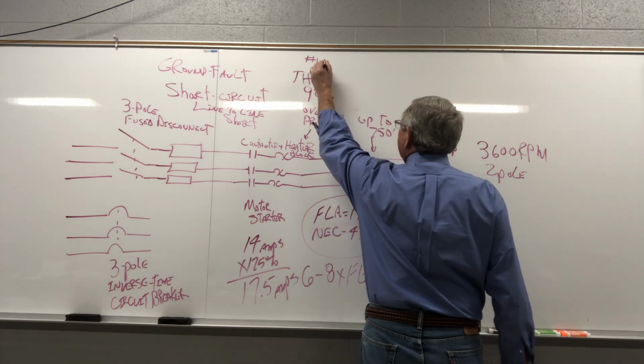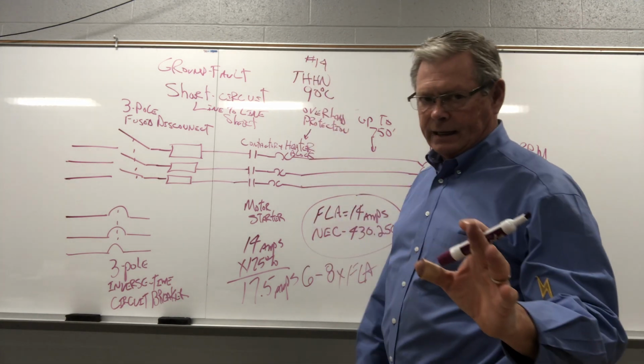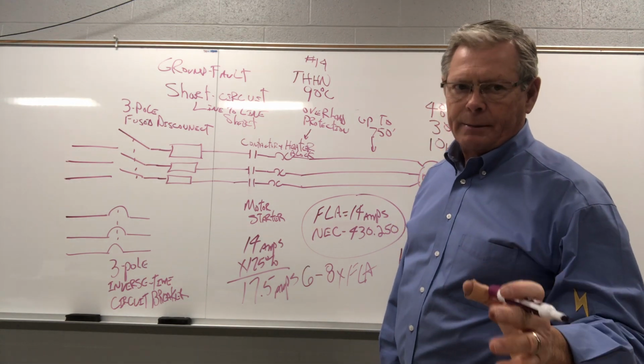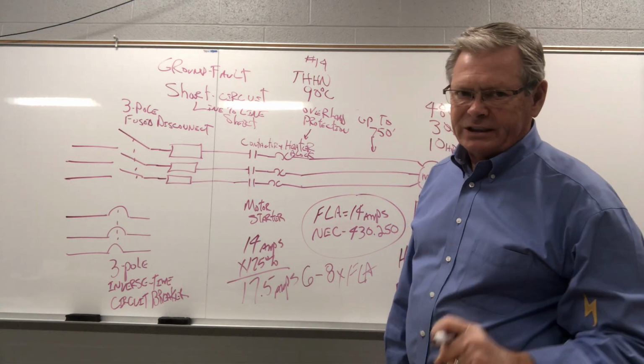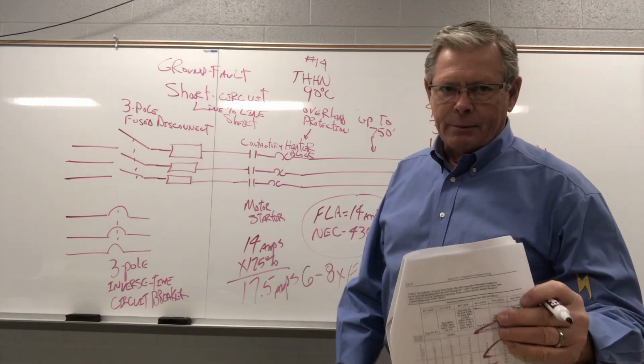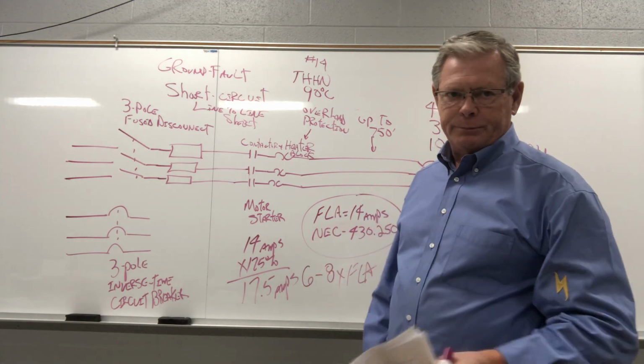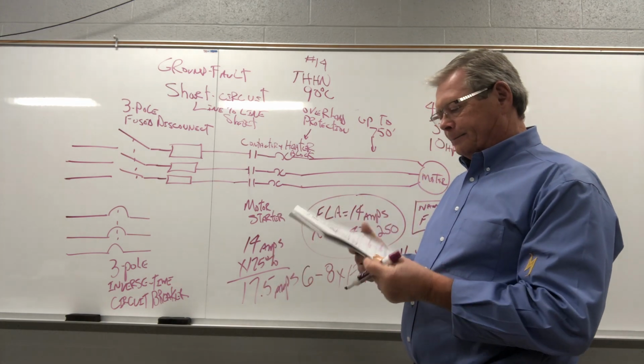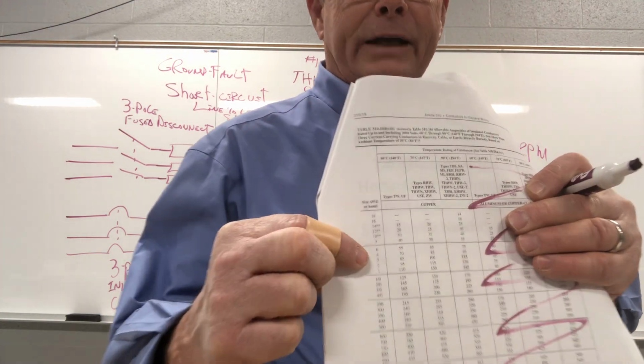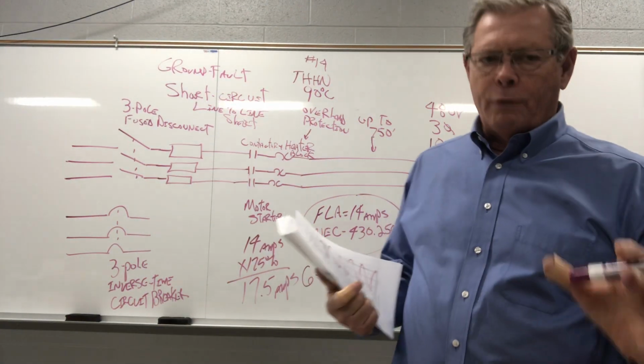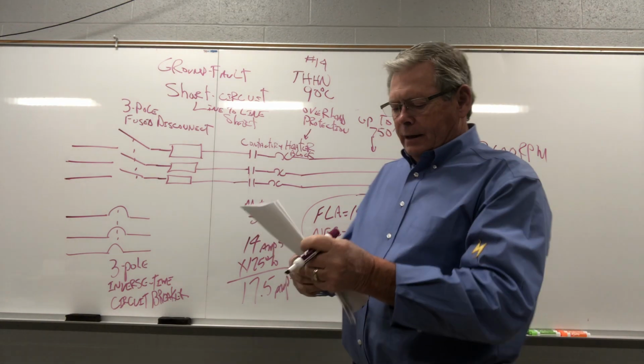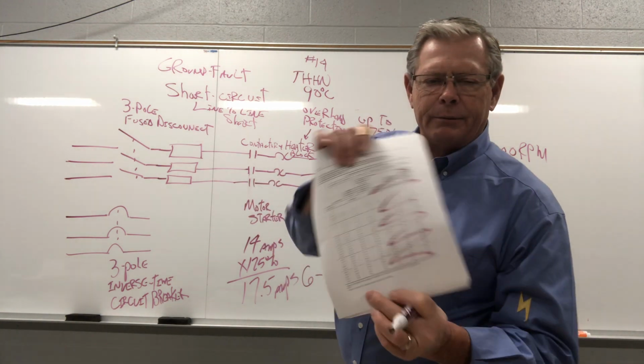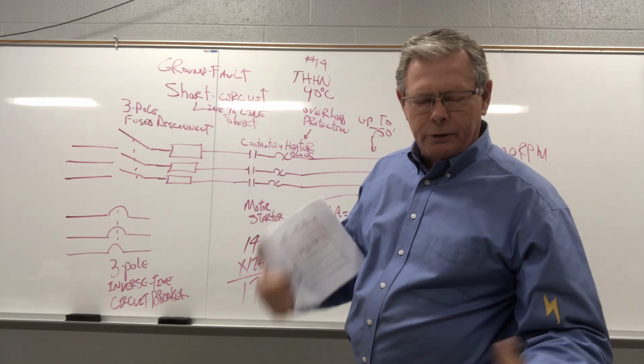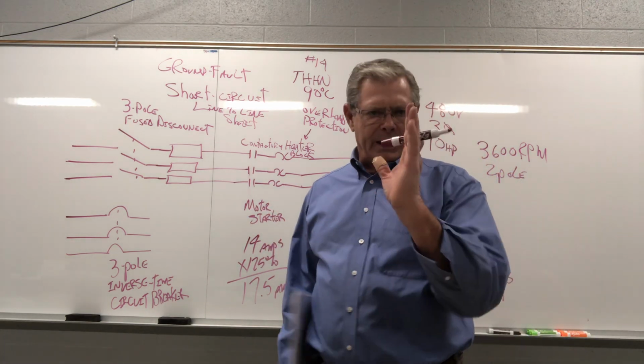Now, we say 14 gauge wire, and that's all we say. As electricians, it's assumed to be copper. If it's aluminum, we must state aluminum. But I don't remember ever pulling aluminum into motors. I've always pulled copper. So, now, there's some double asterisks here, okay? Right there for 14, 12, and 10. Those double asterisks down the bottom of the page takes you to another place in the code book. Here's what it says. Remember that wall I was talking about? Motors are over here and everything else is over here.